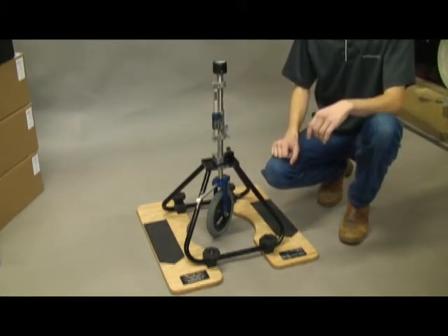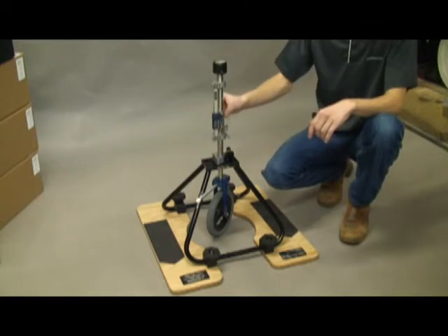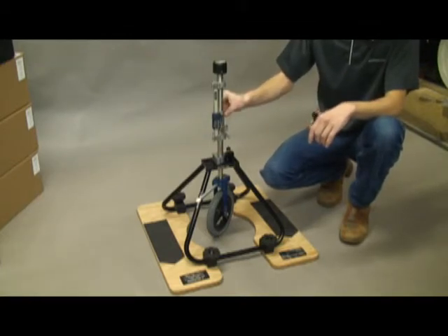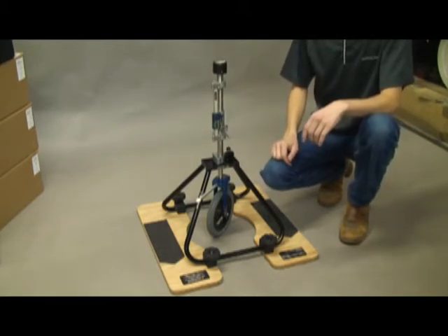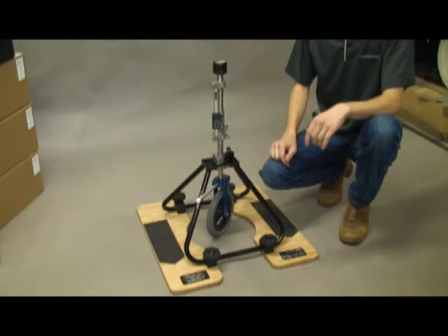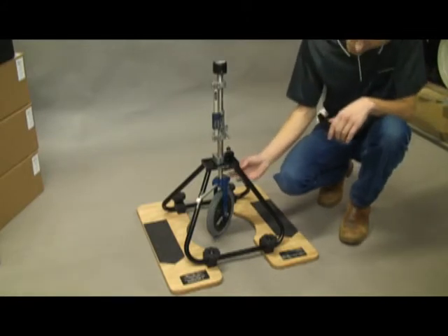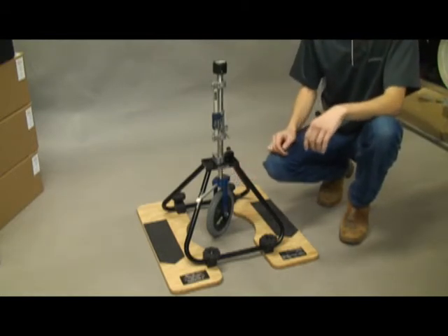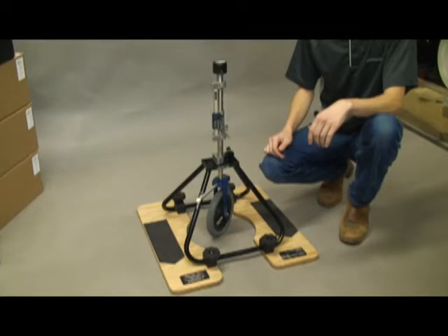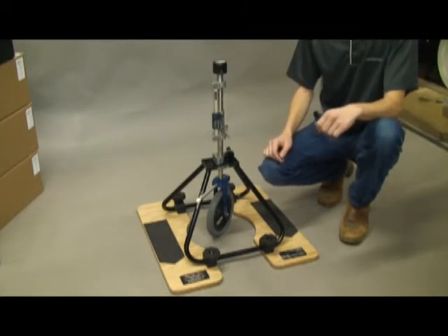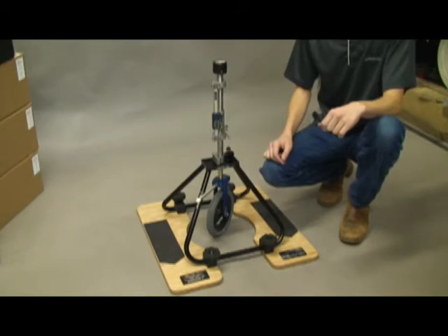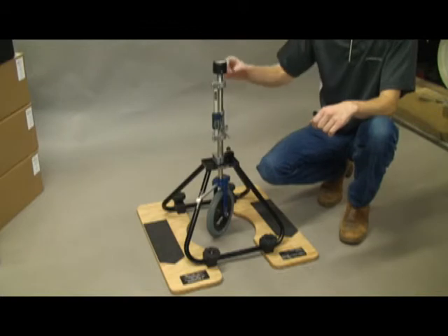The outer spring housing collar is unique to the RP100 series. It surrounds the outer spring housing along the area with the slots for the spring loading handle and provides a polished surface for the spring loading handle to slide against. The inner spring housing moves with the indenter when the spring loading handle is unloaded and contains polished bushings at the top end where the spring loading handle inserts through it, and a receiver at the bottom end for the indenter wheel assembly. The calibration screw is only for use by Beneficial Designs or another authorized test laboratory to calibrate the rotational penetrometer.